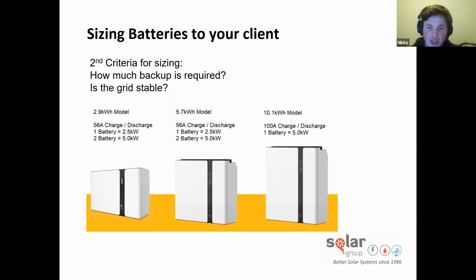Another situation is a farmer. He has an unstable grid and is looking to have a high draw on his backup. This could be a situation where he has both a water pump and a sewage pump. In this situation, we'd recommend 2 of the 2.9, 2 of the 5.7, or 1 of the 10.1 kilowatt hour batteries. This gives you the 5 kilowatt draw.